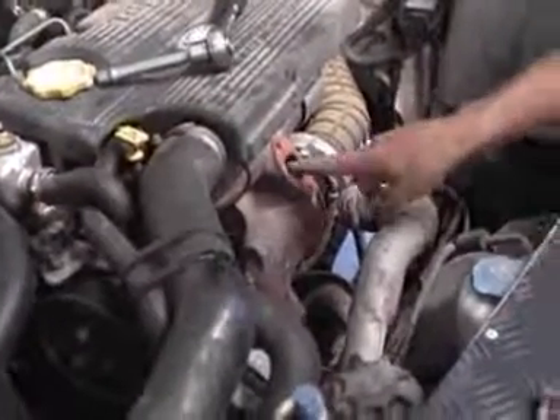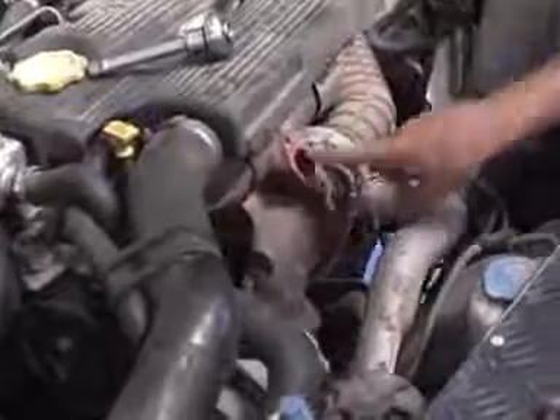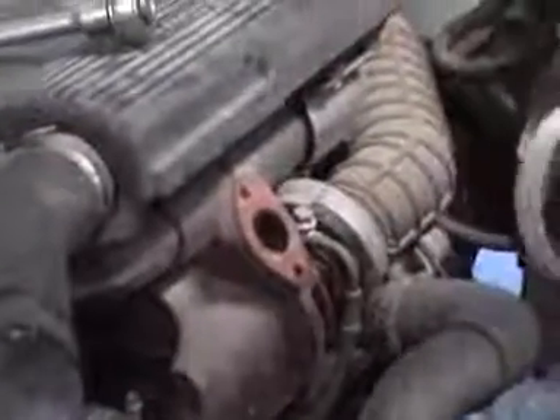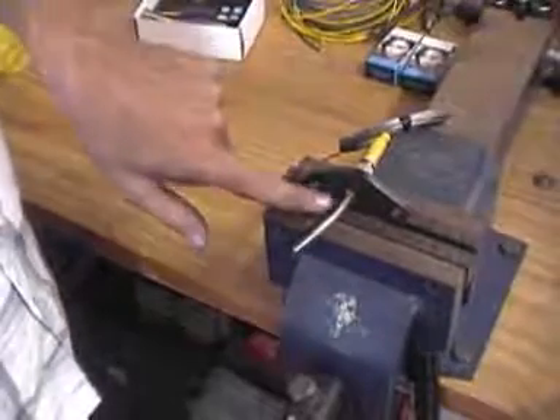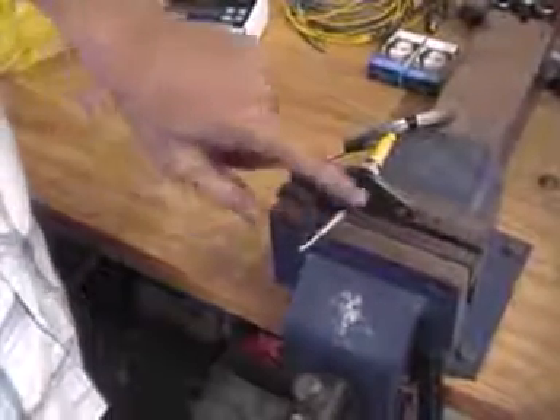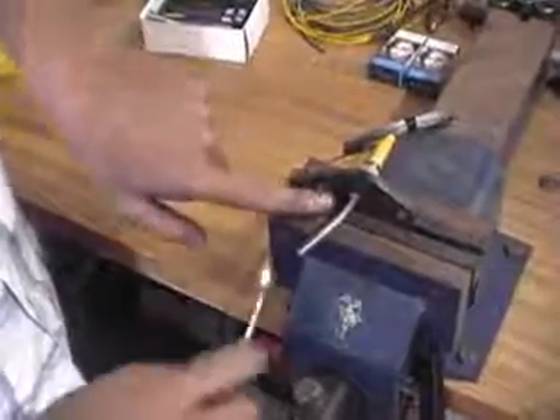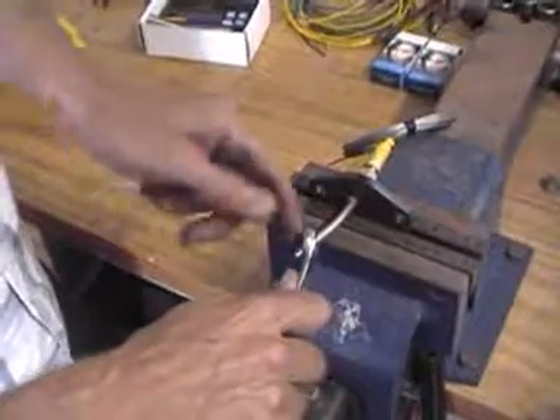As you'll notice, the hole is not straight, it goes in at that angle. So if you try and fit your probe, it's not going to go in. The probe needs to be bent a little bit upwards, just so that it's happy to go in there. Note that it should be bent towards the small side. The hole is not in the center of the plate. The probe must be bent towards the short side. I'm going to bend it a little bit more.